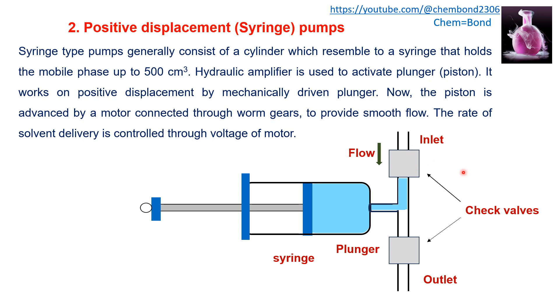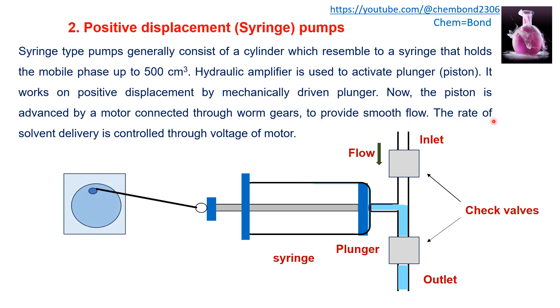In the forward stroke, the mobile phase moves towards the column. The piston is advanced by a motor connected with worm gears that provide a smooth flow. The rate of solvent delivery is controlled by the voltage of the motor — if the voltage is high, solvent delivery is high because the piston moves fast; if the voltage is low, solvent delivery is low because movement is slow.